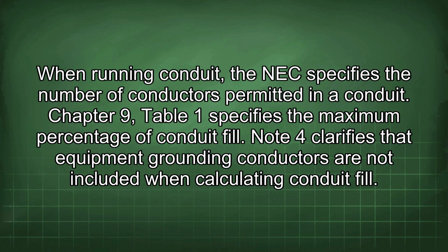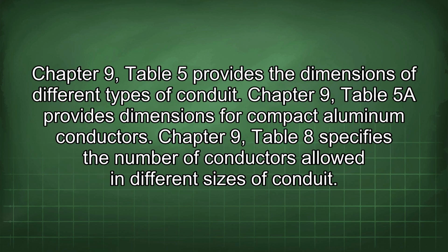Note 4 clarifies that equipment grounding conductors are not included when calculating conduit fill. Chapter 9, Table 5 provides the dimensions of different types of conduit. Chapter 9, Table 5A provides dimensions for compact aluminum conductors. Chapter 9, Table 8 specifies the number of conductors allowed in different sizes of conduit.